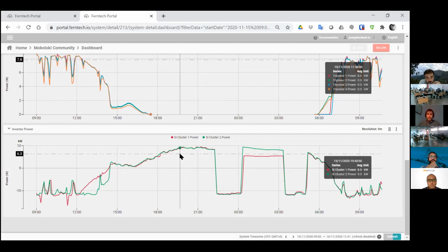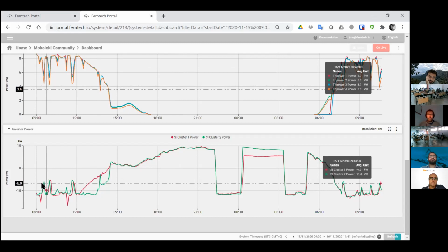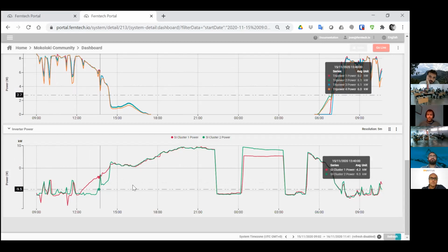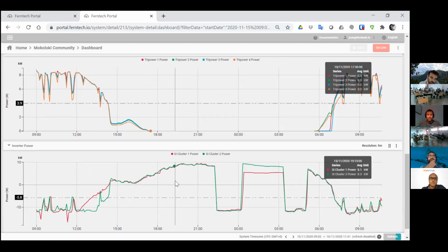Here's one of the things we can say. Well, this mini grid, even if it's AC coupled, the load profile shows that most of the loads are actually at night. The loads are not very high, we're talking about 10 kilowatts. That makes me think that although the mini grid is working and connected, the loads connected during the day are mostly from little businesses, and these appliances have not been connected yet because the loads during the day are really not very high. There are some little peaks here and there, but in general the consumption during the day is not very high. So what makes this behavior in the mini grid?